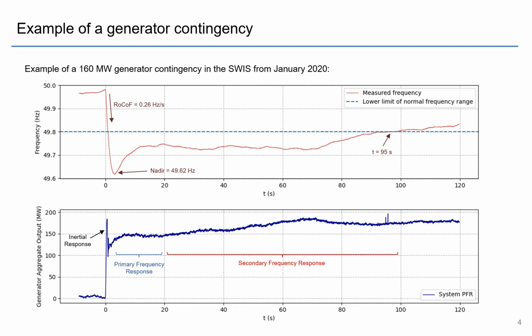Here we see an example of an actual generator contingency. This was a 160 megawatt generator trip in January of this year. You can see the frequency starts near 50, and then you have the event, which I've triggered at 0 seconds. You have a rate of change of frequency of minus 0.26 hertz per second. It drops, hits a nadir of 49.62 hertz, and then recovers to a settling frequency, and then eventually back into the normal operating band.